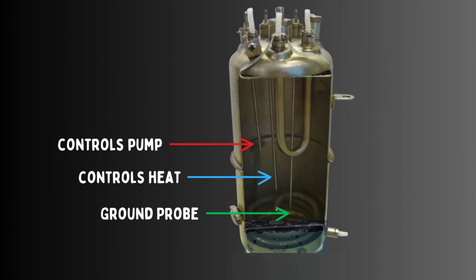Okay, so I think we've covered enough about the actual outcome. Let's investigate why this seems to be happening so much on these machines. In order to do that, we first need to understand more about how these probes function, so we can then work out when or how they are going wrong. The way these probes detect water is by sending through a small voltage of around 2 volts. If the probe is submerged in water, then current will flow through to either the ground probe or the side of the boiler, whichever is closer.